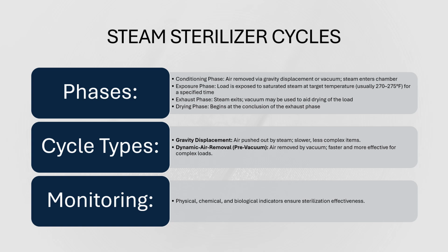The cycles. There are different phases and types of cycles used in high temperature sterilization. The process begins with the conditioning phase. This is where air is removed to allow proper steam penetration. When the steam is being forced into the autoclave, it's conditioning it. It's bringing it up to temperature. It's forcing the cooler air out. It's also taking all that cool air out of the peel packs, out of the instrument sets. So it's conditioning it. It's bringing it up to the right temperature that we need.